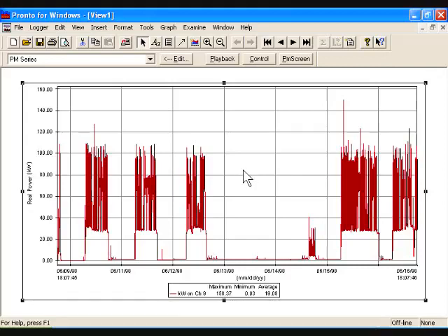It would delay them for 45 minutes to an hour, or they would have to reset the tooling, and they always had to turn off the power to the entire machine and then turn it back on to reset the microprocessor, because it was getting hit with something that would hang it up, like when your computer gets hung up and the only thing you can do is unplug it and then plug it back in.